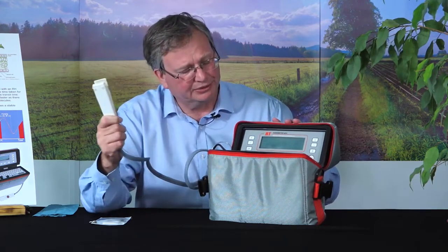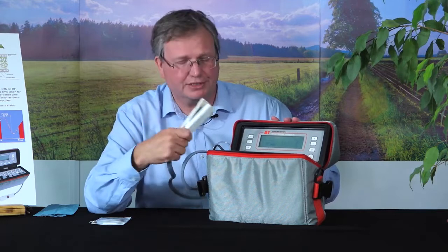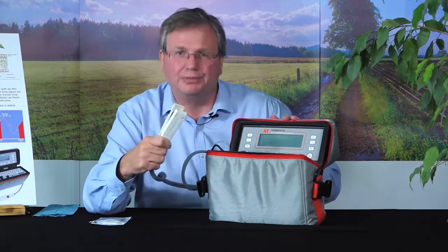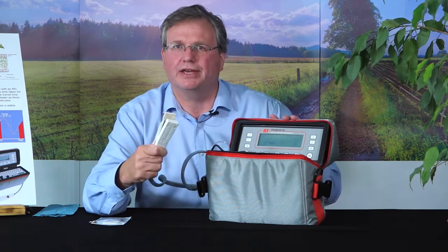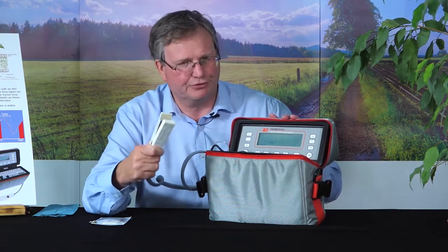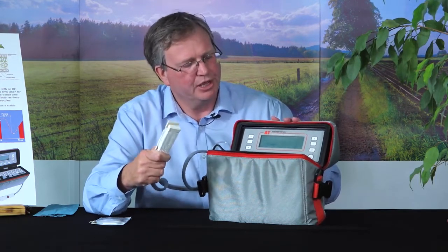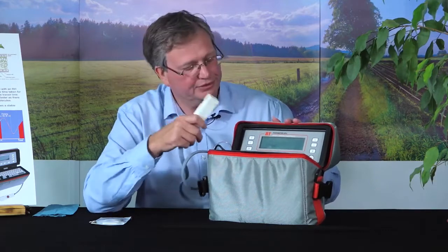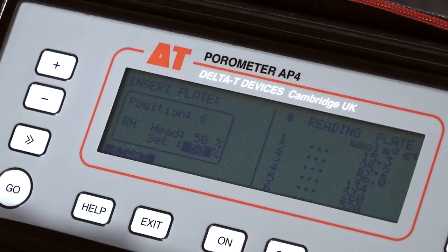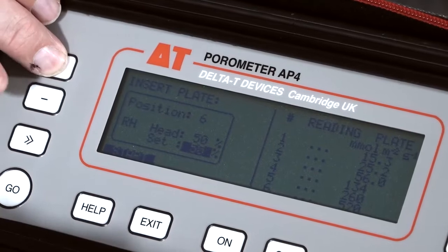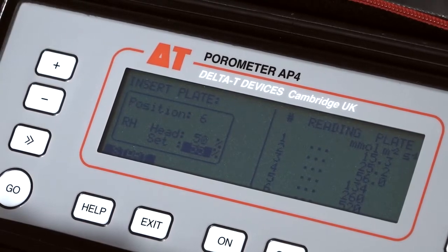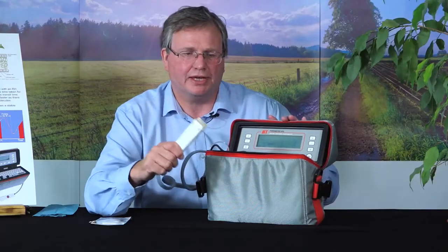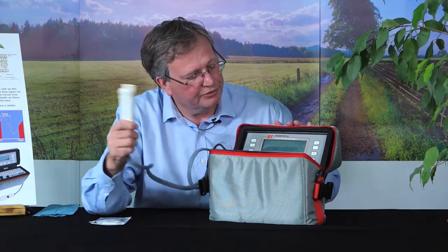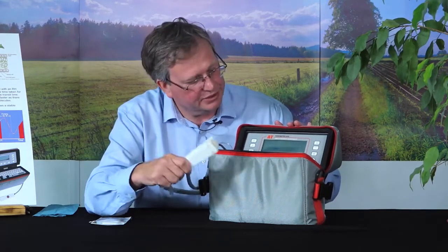Now we're not able to get an accurate measurement of the humidity because the pump is activating. That's drying down the air, so we're not achieving the true value of ambient RH. So we need to disable the pump just temporarily. And to do that, we'll press the plus or the minus key, which deactivates the pump. Now when we move this through the air, we can get a true value of the ambient humidity.